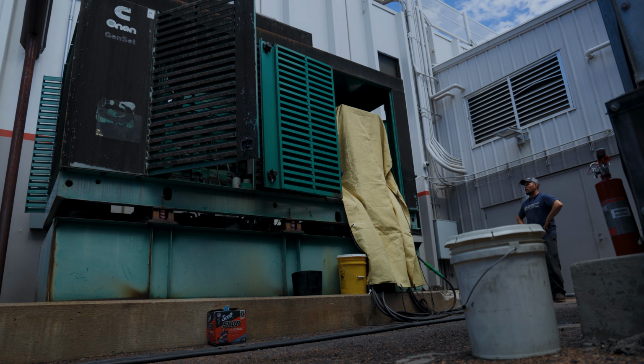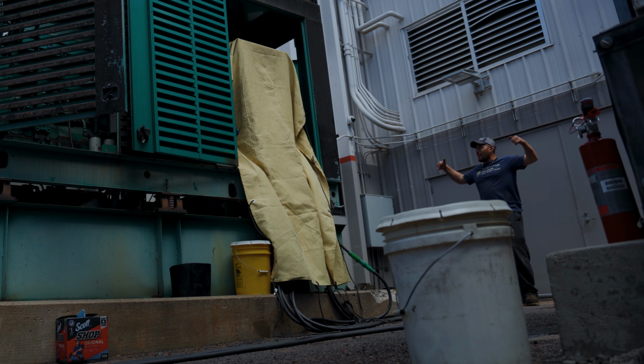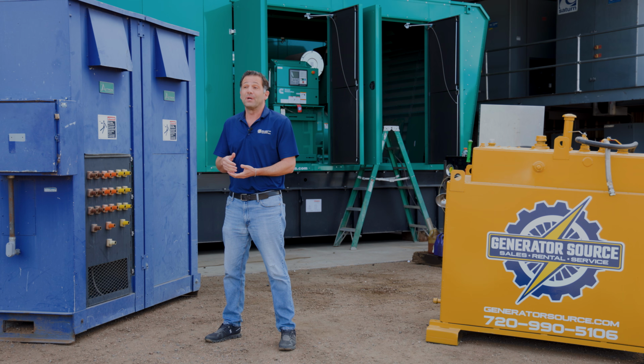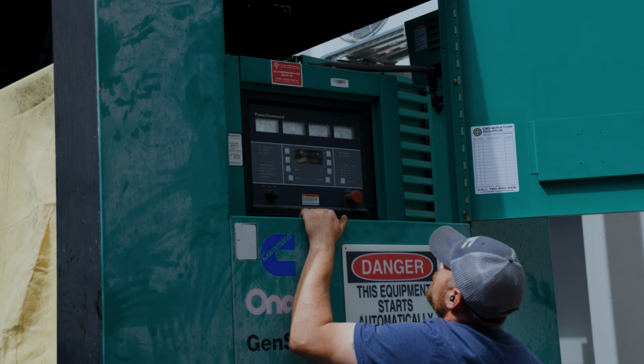The load bank test is to allow the generator to run up to its full operating temperature. What that does is it burns off excess fuel and excess carbon, and will shake out any issues with the generator like leaks or vibrations.